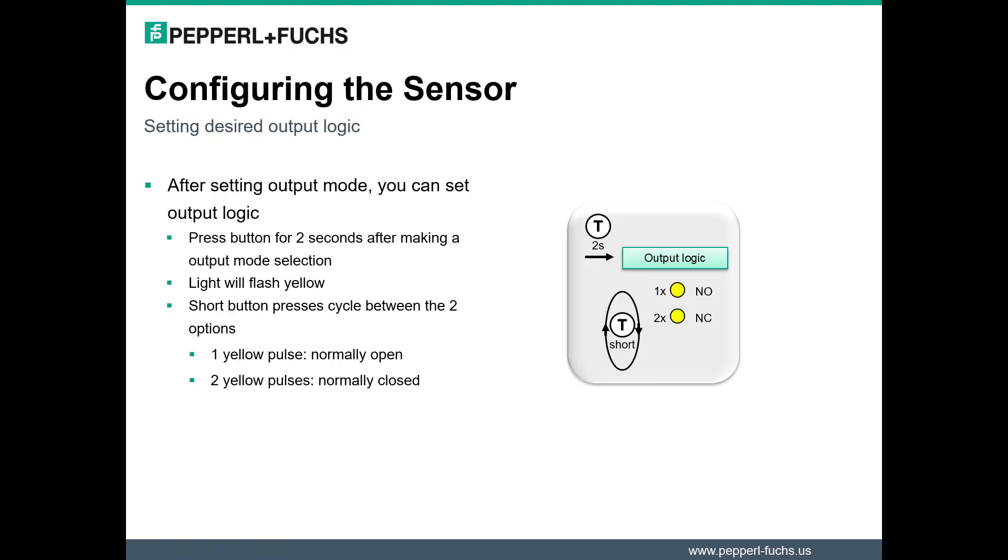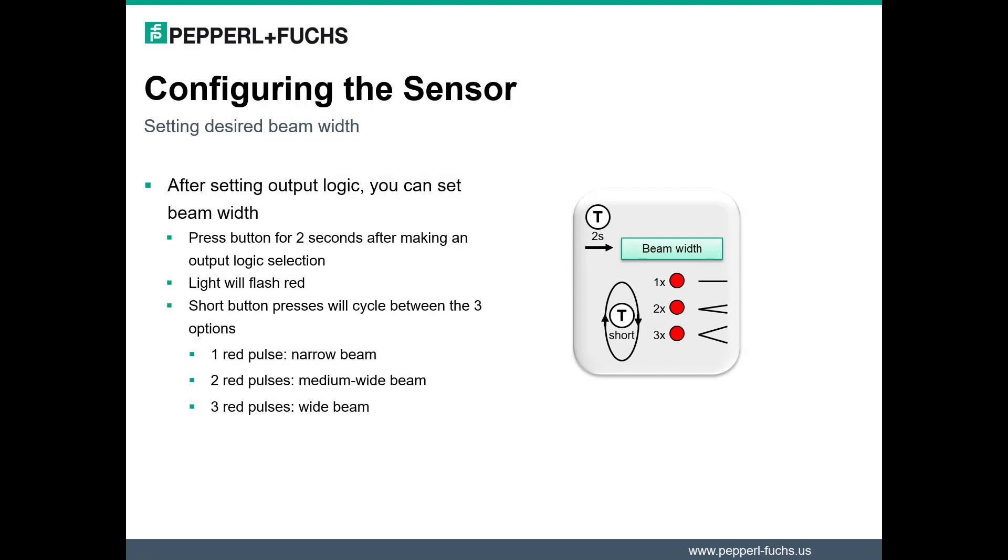After you have chosen your output mode, we can now set the output logic. To move on to the output logic, hold the push button for 2 seconds until you see the light begin to flash yellow. You can then cycle between the two options using short button presses. One yellow pulse indicates normally open, and two indicate normally closed.